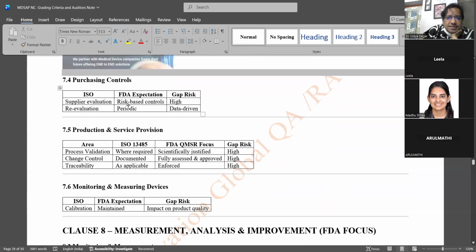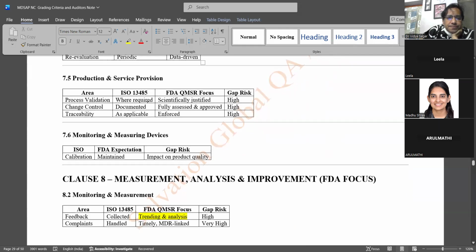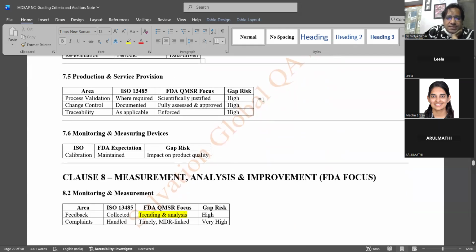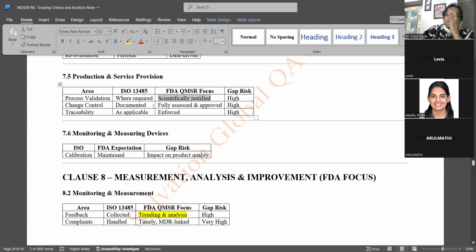Purchasing controls, high risk-based controls. Here we do supplier evaluation in ISO, but you need to link risk also. All in production and service control, they are high risk compared to ISO. Process validation: when I say scientifically justified, you need to use a lot of logic and statistics. Any data without statistics, for US FDA, is data that can be dumb. When you use statistics, it is scientifically valid.